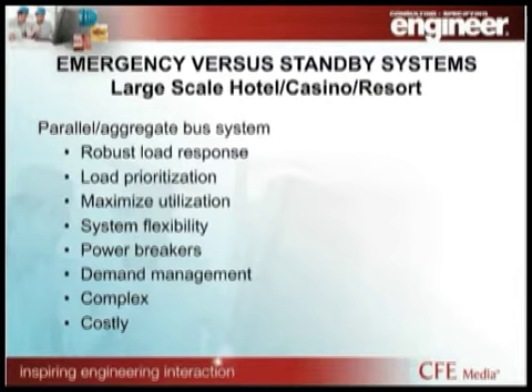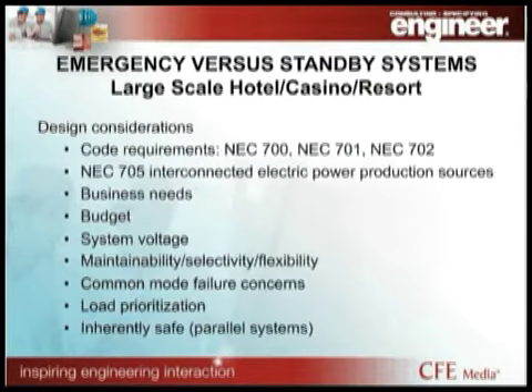The other is, it is expensive for a property operator who, if their casino is down, is going to lose multi-millions of dollars an hour. They're usually willing to make the investment, has been our experience. When you start to look at the design considerations, we talked about code requirements, NEC 700, 701, 702. 705 becomes important when you look at doing closed transition paralleling. We do a lot of closed transition, both domestically and internationally. The benefit of the closed transition is you can go between the generators and the utility without disrupting the load. That becomes a huge benefit to the property, particularly when an open transition bump creates all kinds of operational headaches.